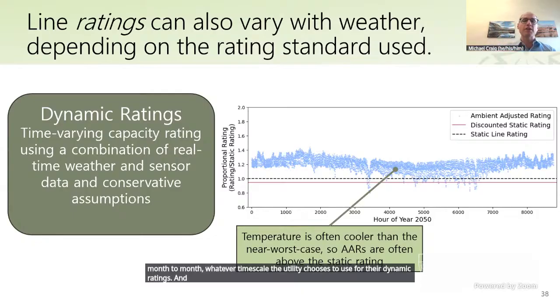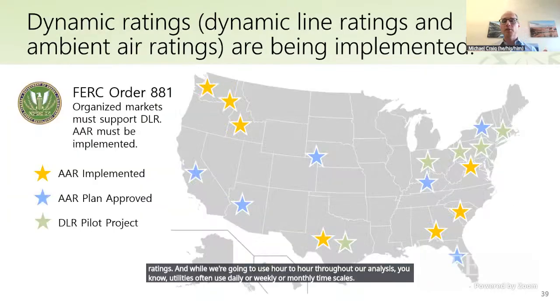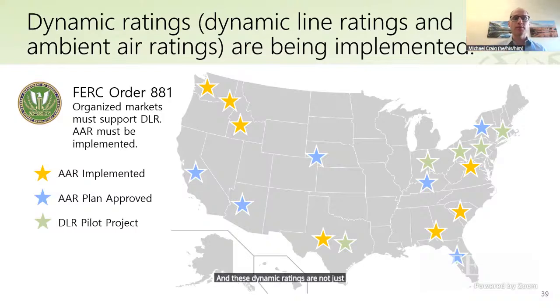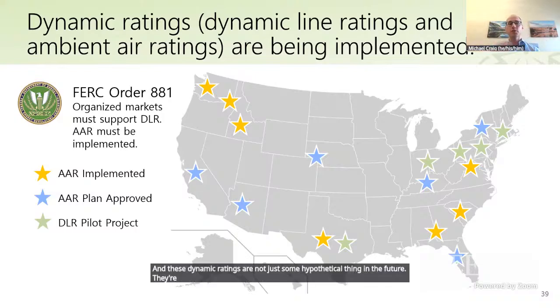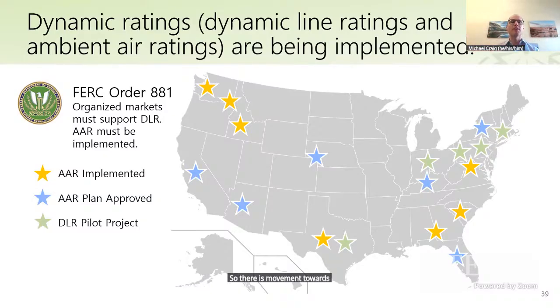While we're going to use hour to hour throughout our analysis, utilities often use daily, weekly, or monthly timescales. These dynamic ratings aren't just hypothetical for the future. They're being used across the country. Ambient air ratings, a type of dynamic rating, are already used in Texas today by ERCOT, and there's a FERC order that says all markets must support dynamic line ratings.